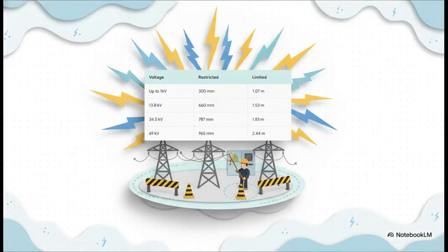Now, let's put some real numbers to this, because when you're working near exposed, live conductors, these approach boundaries are literally a matter of life and death. Say you're near a 13.8 kV system. Your restricted approach boundary is exactly 660 millimeters, and your limited approach is 1.53 meters. Only the issuer, geared up in rated PPE and using an insulated hot stick, is allowed to breach those restricted boundaries to isolate a line. So whatever barriers you're setting up on site, they have to visually enforce these exact clearances. No exceptions.